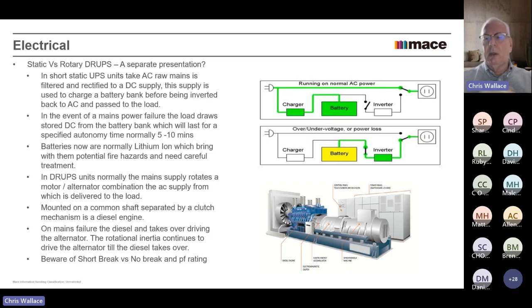the motor generator block, you're using the inertia to spin it down, and as the load is pulling on the alternator, it's slowing down. And if you've got too much load on it and you're pulling it off too quickly, you'll actually go to an under voltage situation quickly. So you've got to be very careful.